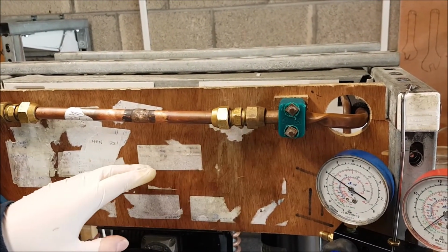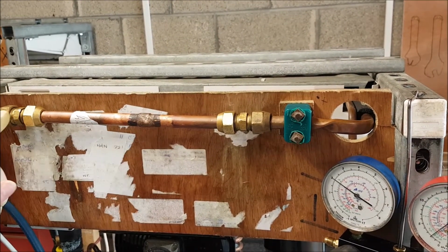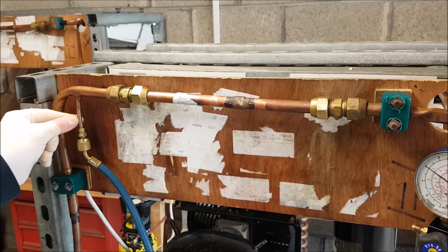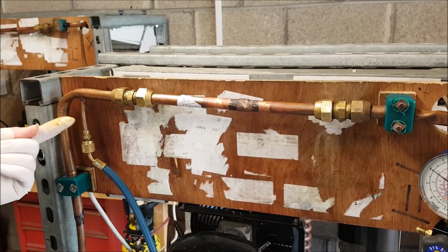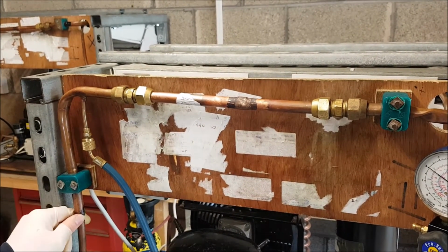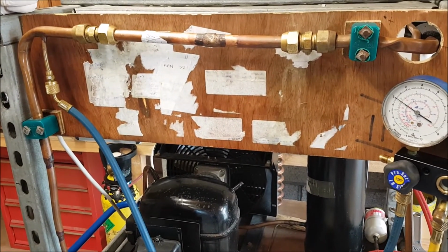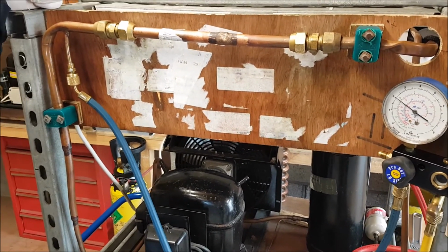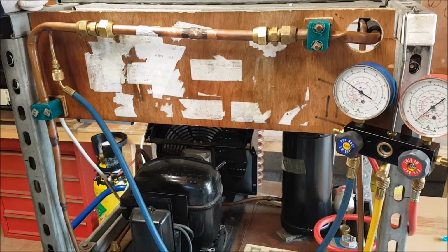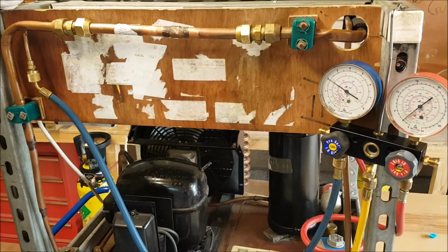If there's oil on the outside of the pipe, the only place that can come from is the inside of the pipe. So again, you look at all the obvious areas and you use your fingers to see if there's any traces of oil around the actual system itself. If you can see any oil or feel any oil, then it's coming from the inside. The other thing we use is our ears, so we're listening to see if we can hear any subtle signs of hissing noises coming out. And we use our eyes, so we're looking at our pressure here to see if that's dropping anywhere.